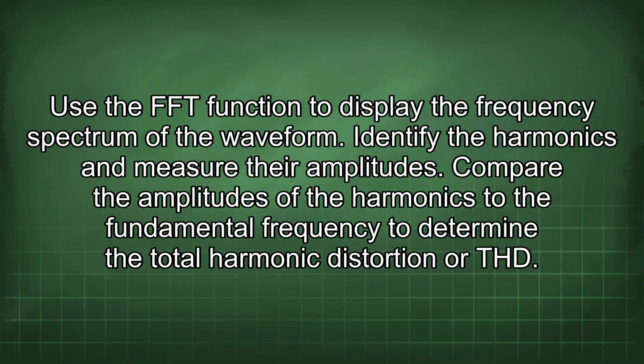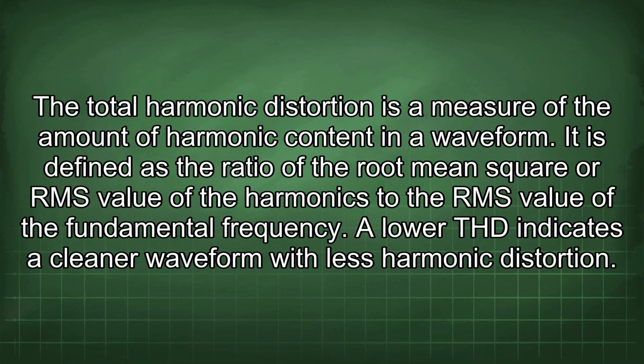Compare the amplitudes of the harmonics to the fundamental frequency to determine the total harmonic distortion, or THD. The total harmonic distortion is a measure of the amount of harmonic content in a waveform. It is defined as the ratio of the root mean square, or RMS, value of the harmonics to the RMS value of the fundamental frequency. A lower THD indicates a cleaner waveform with less harmonic distortion.